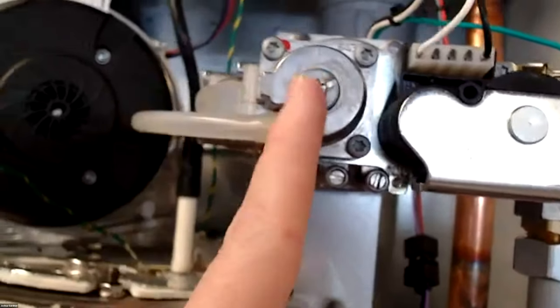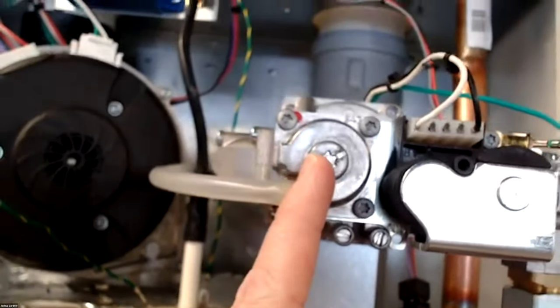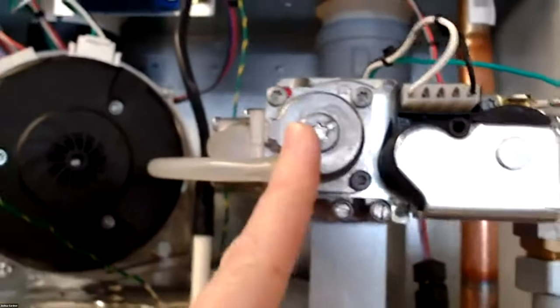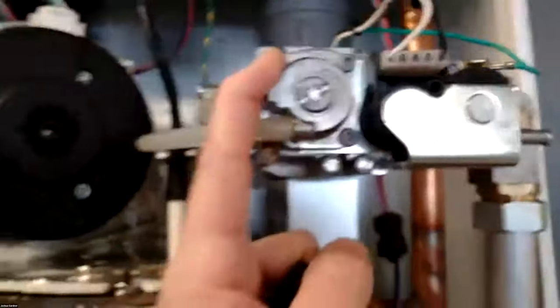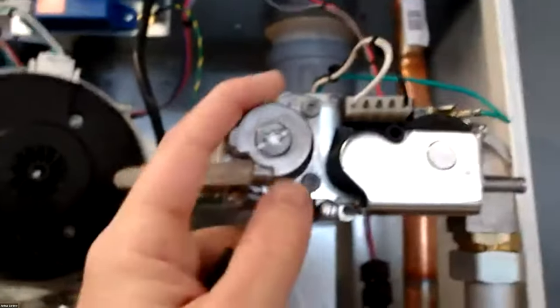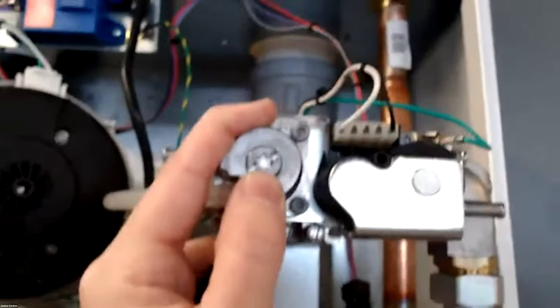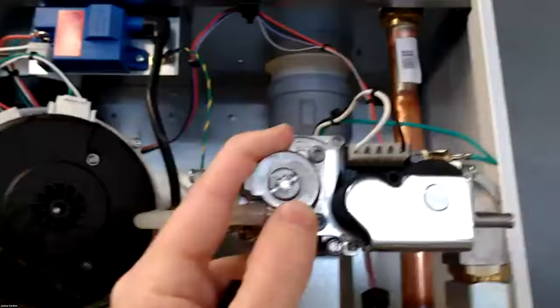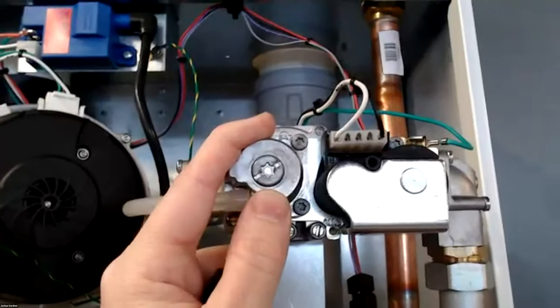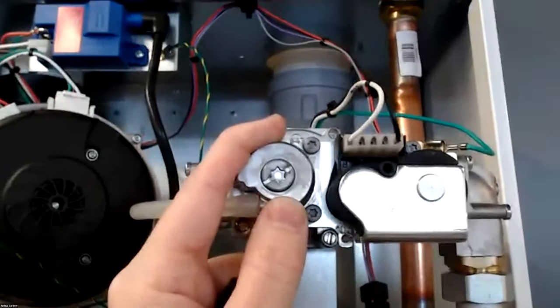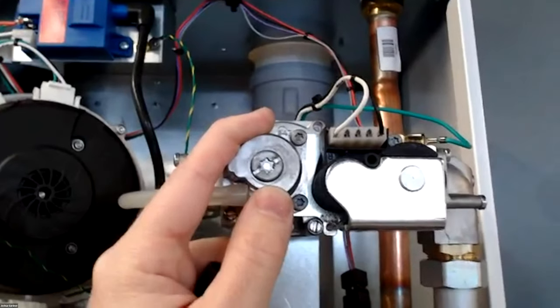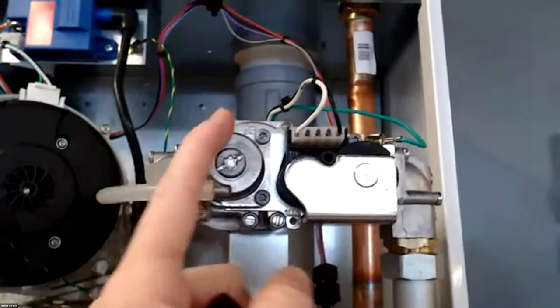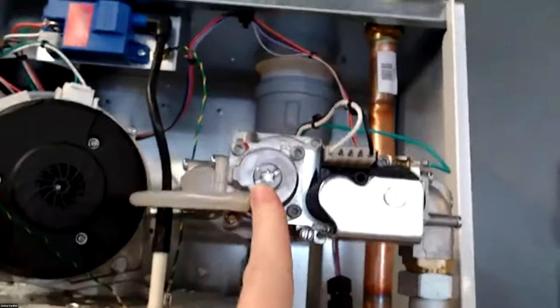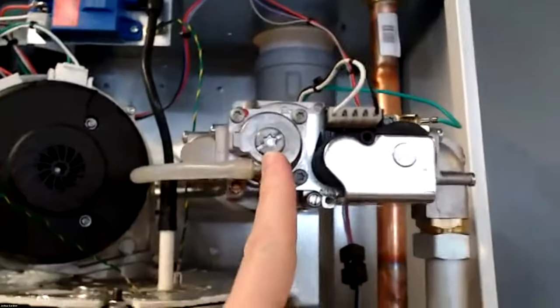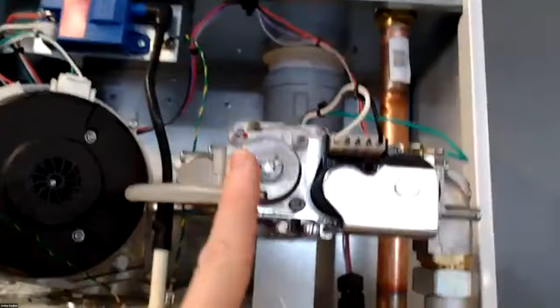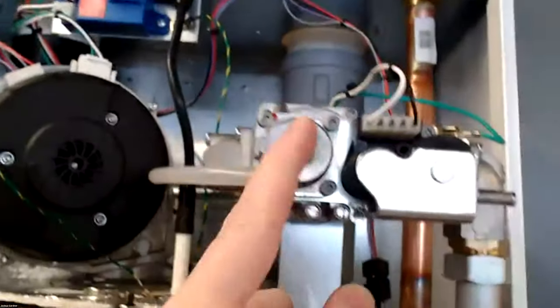Now, this is the offset screw. We'll go through it, but this offset screw is what we use to adjust the pressure coming out of the gas valve. The only times that we're going to have to adjust this is on some propane applications where we're running too lean and we've opened our throttle all the way. We'll then sometimes have to get into this to adjust it. This is our very sensitive screw. And I would recommend if you are trying this for the first time, call us, call tech support. We'll walk you through this.